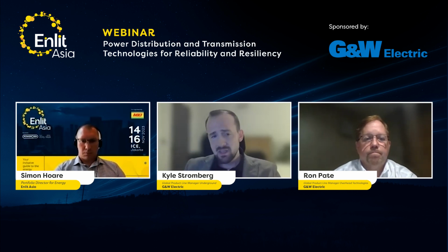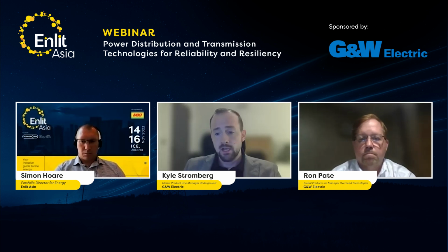Again, minimizing the opportunities for something to happen that could create an ignition event. And last but not least, the CLiP product that John mentioned, that really cool system protection device. If you're not familiar with that device, it has the capability to interrupt faults much more quickly than a traditional circuit breaker. It can clear a fault in half a cycle or less, in parallel with reducing the amount of let-through energy. So those two things together can do wonderful things for reducing stress on the system, preventing things like arc flash and blast downstream.